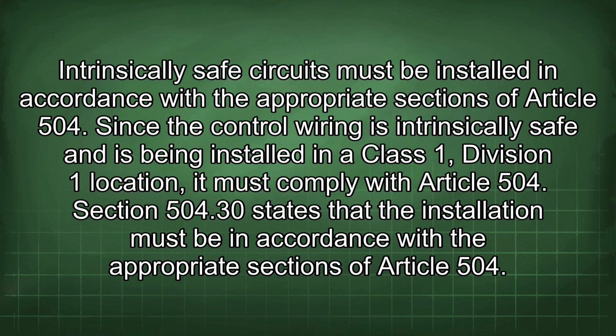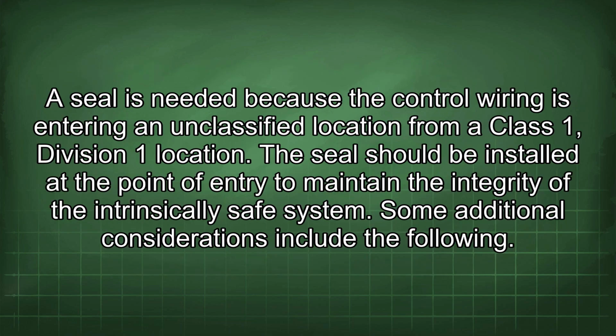Since the control wiring is intrinsically safe and is being installed in a Class 1, Division 1 location, it must comply with Article 504. Section 504.30 states that the installation must be in accordance with the appropriate sections of Article 504. A seal is needed because the control wiring is entering an unclassified location from a Class 1, Division 1 location. The seal should be installed at the point of entry to maintain the integrity of the intrinsically safe system.